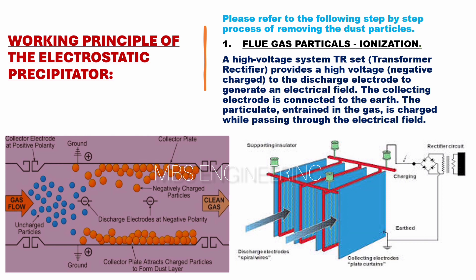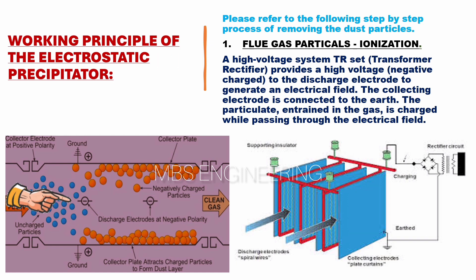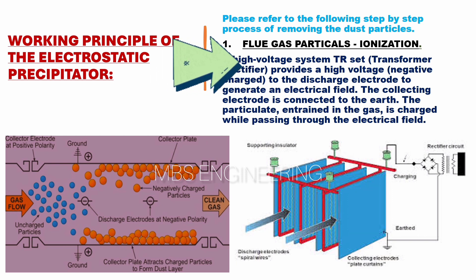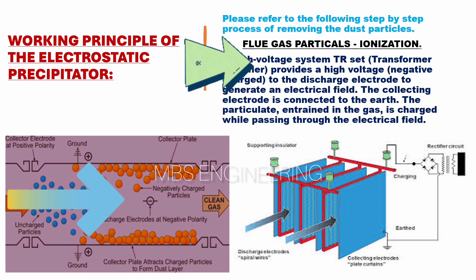The first step of the electrostatic precipitator's working principle is the ionization of the dust particles. Discharge electrodes are placed in between the collecting electrodes, and then connected to the high voltage TR set, or transformer rectifier, which provides a high voltage, negatively charged supply to the discharge electrode to generate an electrical field. The collecting electrode is connected to earth. The particulate entrained in the gas is charged while passing through the electrical field.